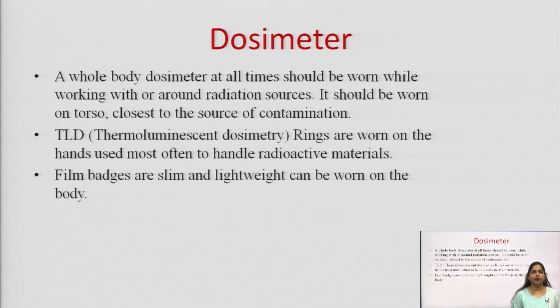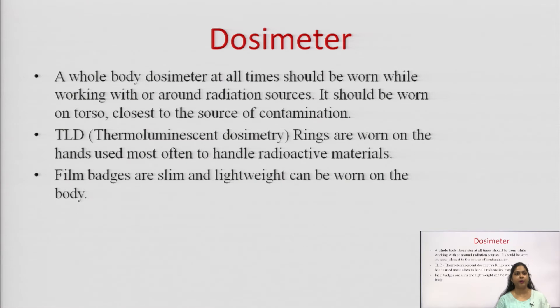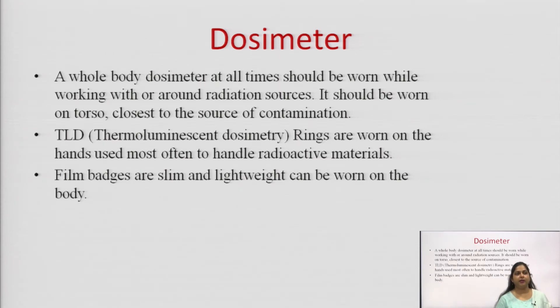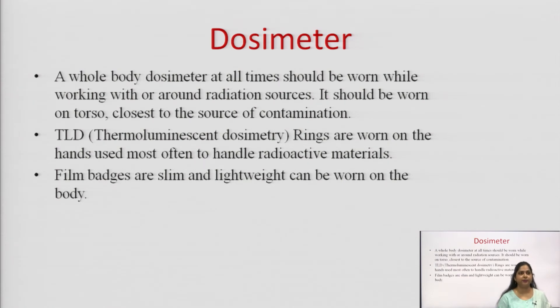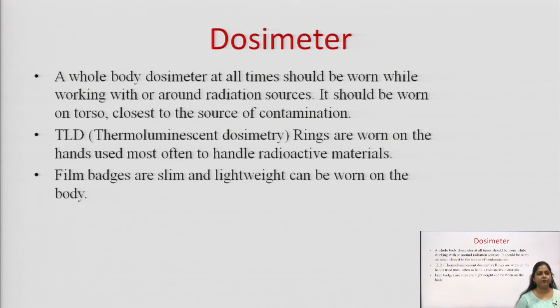A whole body dosimeter is to be worn while working with radiation sources. Those continuously working with radioactive compounds are provided with different types of dosimeters. These dosimeters can be worn on the torso area or closest to the source of contamination — on the fingers, wrist, or as a card on the torso. Thermoluminescent dosimeters are worn as rings on the hands, since hands are often the most exposed when handling radioactive material.